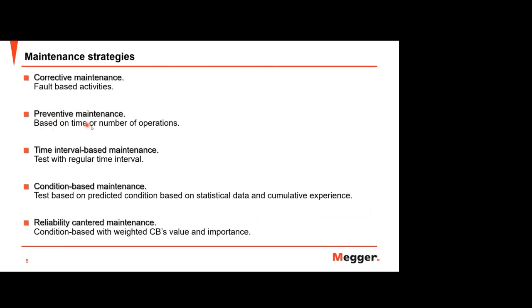Yeah, this is based on the time or number of operations. So you do maintenance on your circuit breaker based on how many years you have already used it, and how many times this breaker has operated on your system. So the longer and the more the breaker operates, the more you need to do maintenance to prevent any sudden failure of the circuit breaker. So this is, we can say, regular, but based on how old your equipment is.